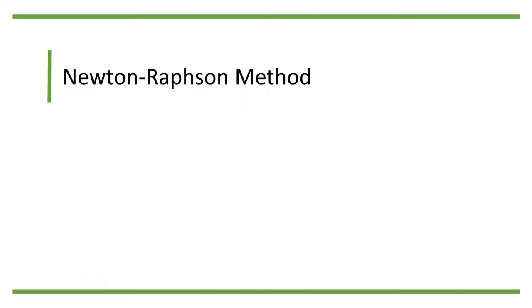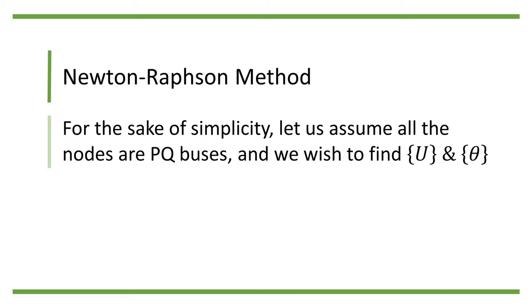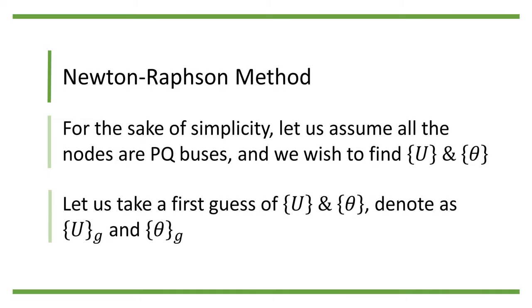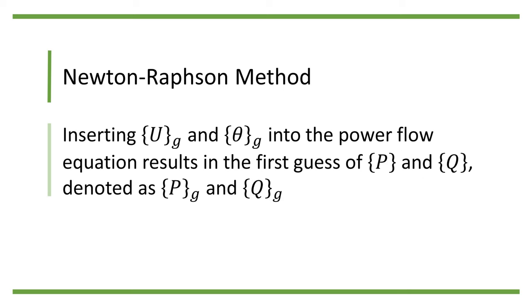To demonstrate how the Newton-Raphson method works, assume for the sake of simplicity all the nodes in the power system are PQ buses, and we solve for the voltage magnitude and phase angle for each node. We do so by starting with an initial guess of U and theta, which we call U_g and theta_g. Next, let us insert U_g and theta_g into the power flow equation. This will result in the first guess of P and Q, denoted as P_g and Q_g.